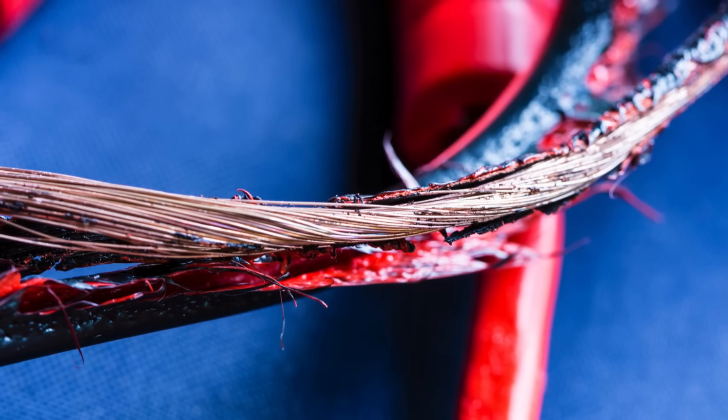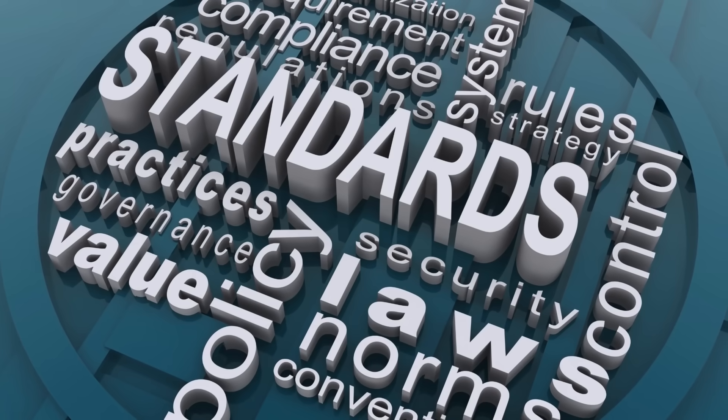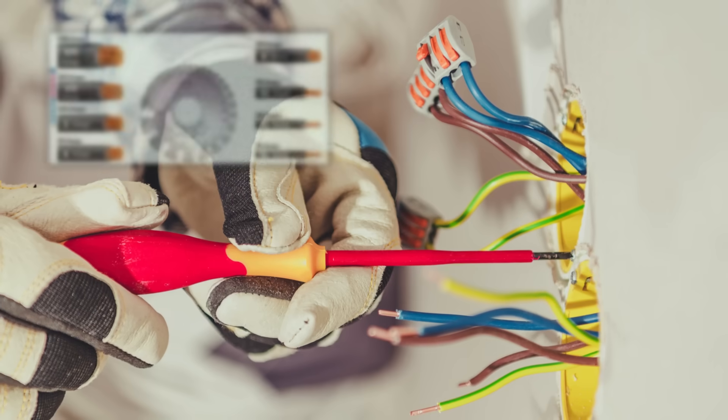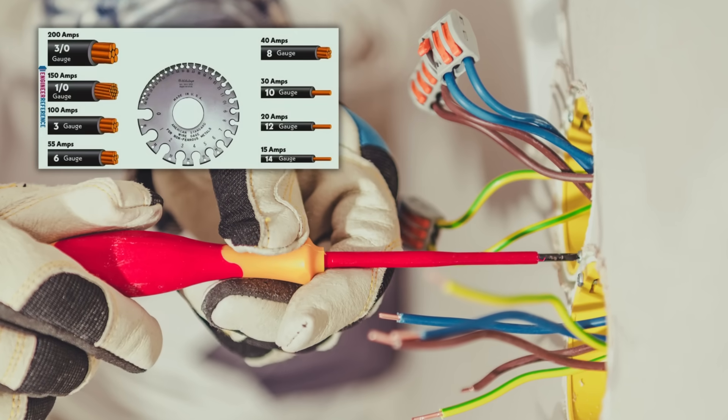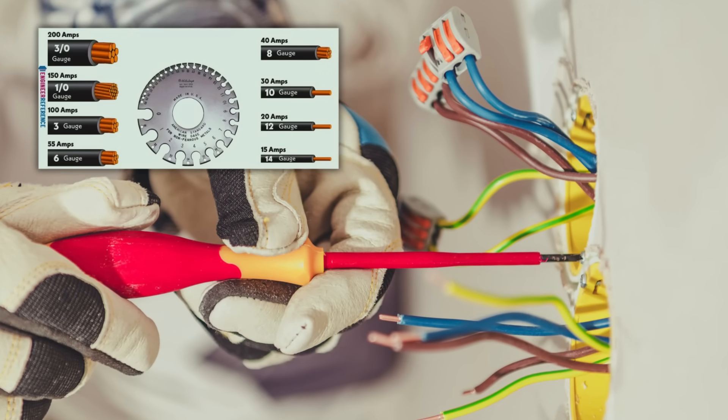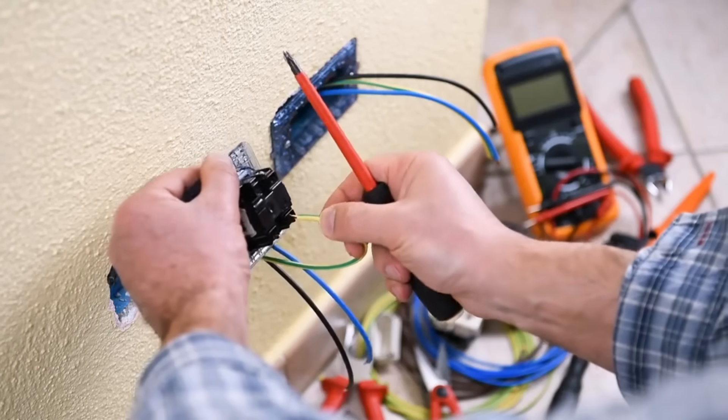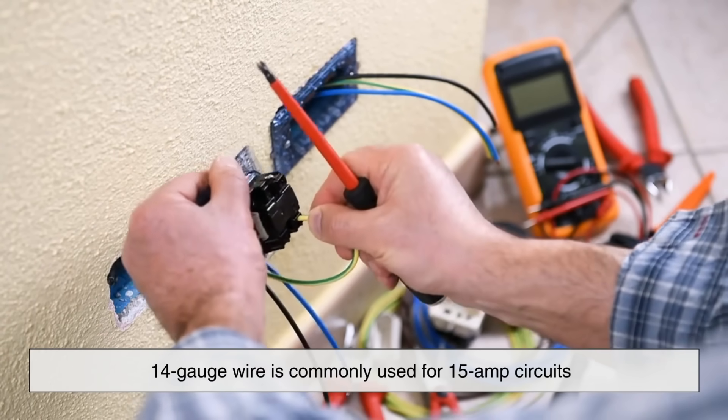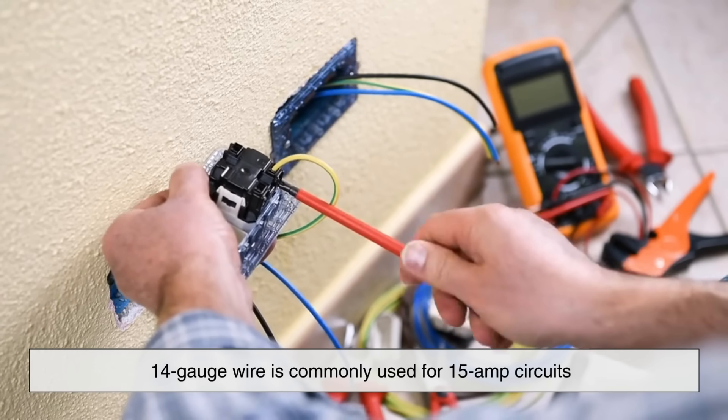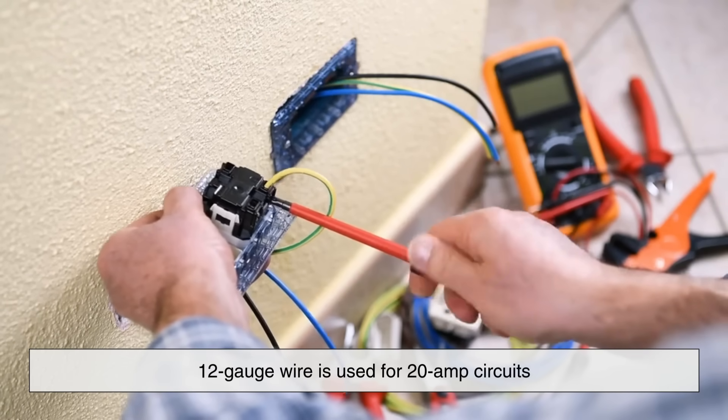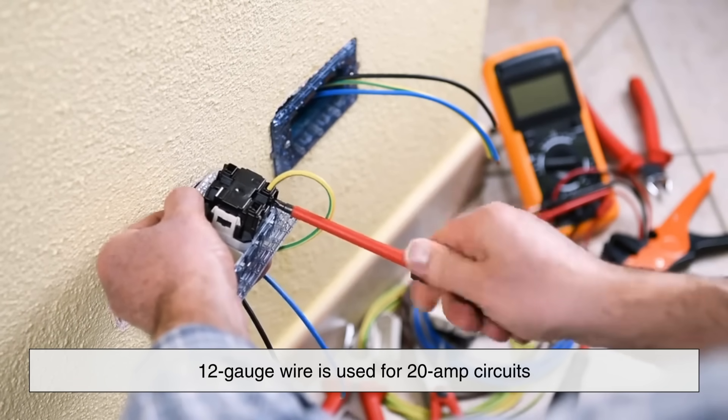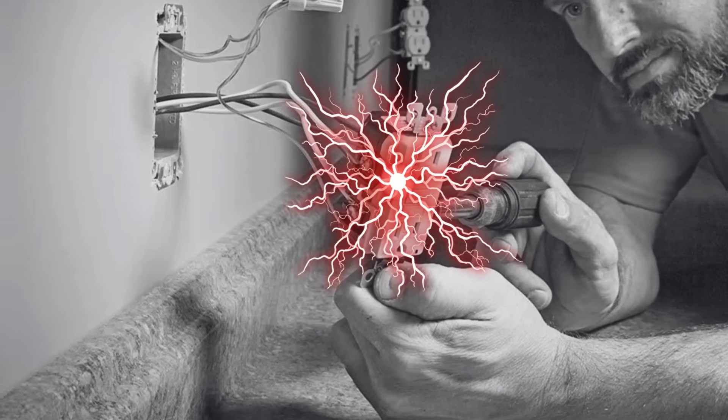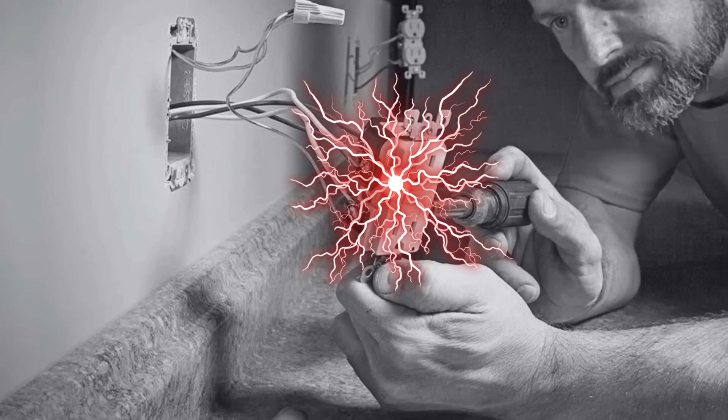This can cause the wire to overheat and the insulation around it might start to degrade. That's why codes and standards exist to guide us in selecting the proper wire gauge for specific current ratings. For example, in residential wiring in the US, a 14 gauge wire is commonly used for 15 amp circuits, and a 12 gauge wire is used for 20 amp circuits. Going beyond those limits is not just bad practice, it's dangerous.